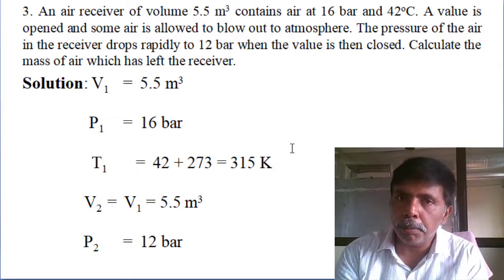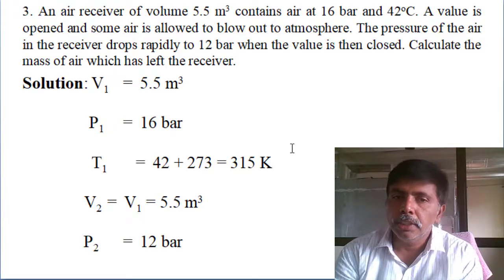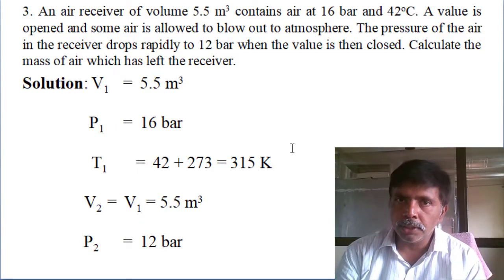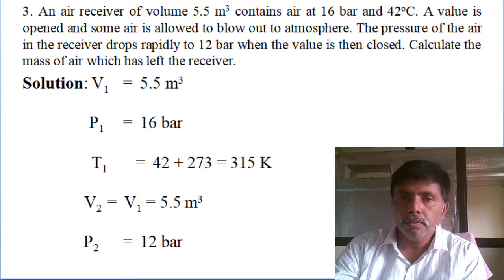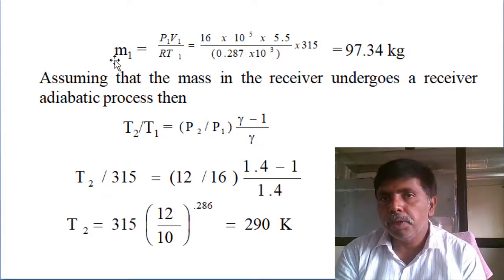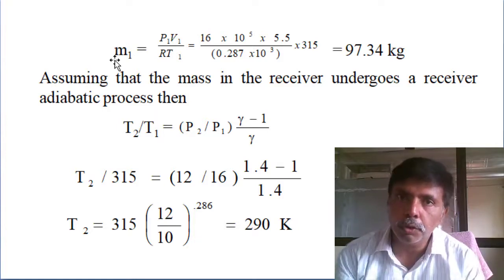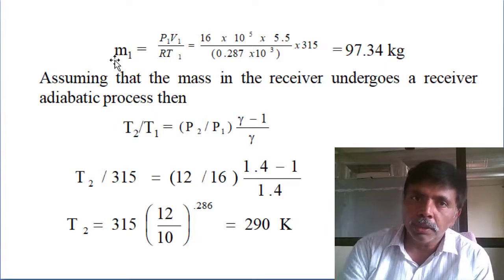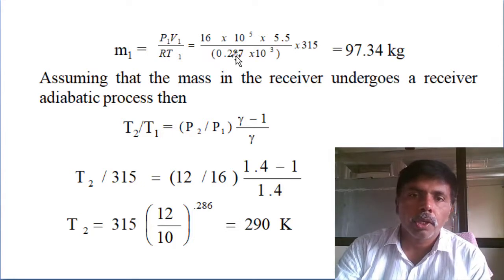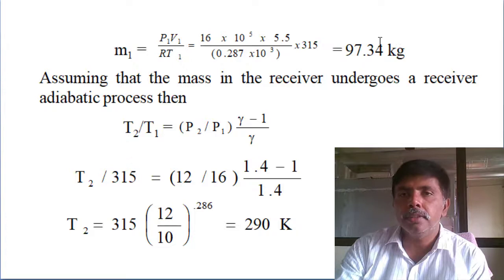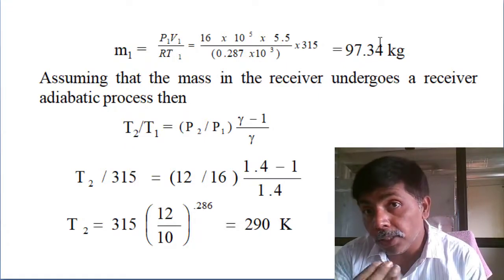Using the basic equation PV = mRT, the gas constant R for air = 8.314 / 29 = 0.287 kJ/(kg·K), where 29 is the molecular weight of air. Substituting these values gives the initial mass of air in the receiver at 16 bar.